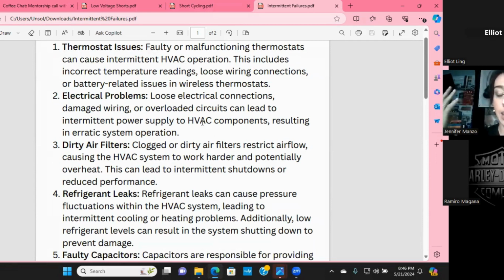One of my students is struggling with this right now. She has a system that, while she's there, everything is beautiful. I mean, she's got 40 degree vapor saturation, 92 degree liquid saturation, a 10 degree superheat, a 9 degree or 14 degree subcool. She's got everything looking beautiful. But when she leaves, a few hours later the suction line ices up and they've got to shut it down.